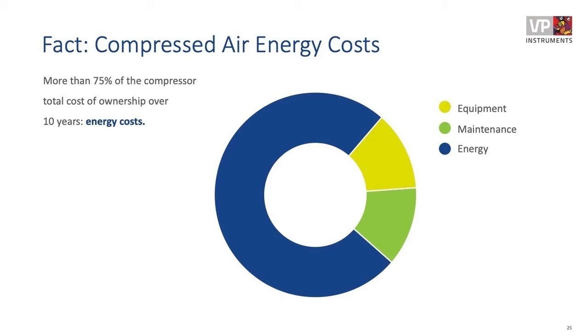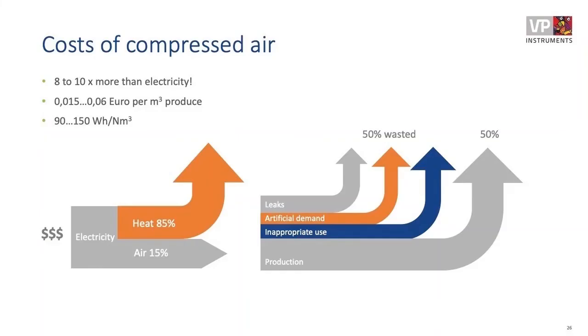Now, where does all this energy you put into the compressor go? A lot of it is actually converted into heat, and only 15% approximately comes out in the form of compressed air, which then enters the pipe network. What you will then see is that only 50% of that part is used usefully, and 50% is in general wasted by leaks, by artificial demand, by inappropriate use of compressed air, like cleaning your truck or sweeping the floor, or by cooling bearings, as Bo showed also. So what can you do about this?